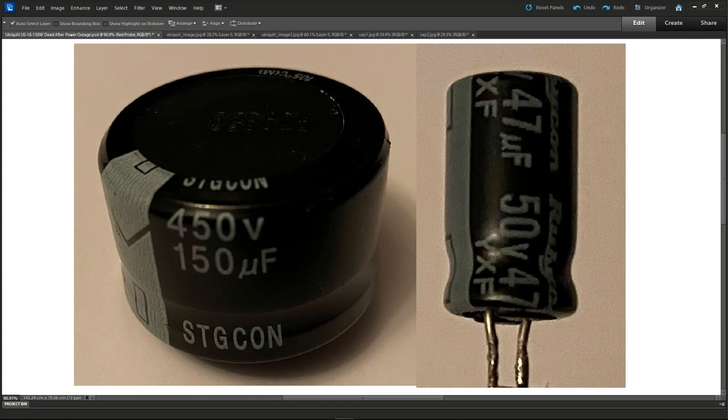After I got it working, I checked online, and apparently this is a known issue with these switches, that the filter capacitor on the left is not of the greatest quality and that it can fail. I've seen another video with another YouTuber who had a similar situation with his switch, and it was visible when he opened the cover off the switch. He could see physical damage to the main filter capacitor, and could immediately identify that as being the problem and replace just that, and that's what got his working again. So I suspect it's probably the same in this case, that I've changed the startup cap for no reason. But again, I was just playing the odds on this.